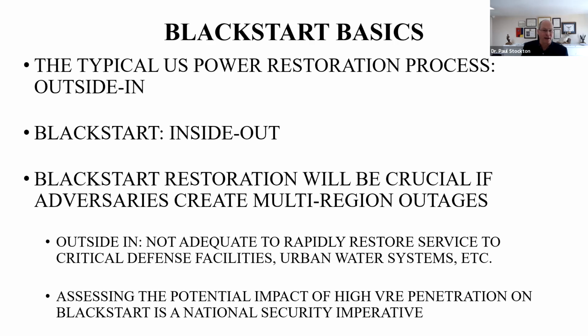I want to provide a level set here of what constitutes a Black Start. Typically, almost all past major US power outages, we've restored power by taking power from outside the blacked out area, where the grid is still up and running and generators haven't tripped off, and we bring that power into the blacked out region to restart generators, serve critical load, and bring the grid back up.